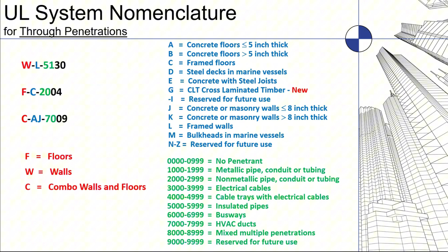And this is what a listing looks like. In this particular case, it's a CAJ - a combination, concrete or masonry wall according to the AJ. It's a 12, in the 1000 series, for a metallic pipe, conduit, or tubing, and it's the 35th test done in that series.